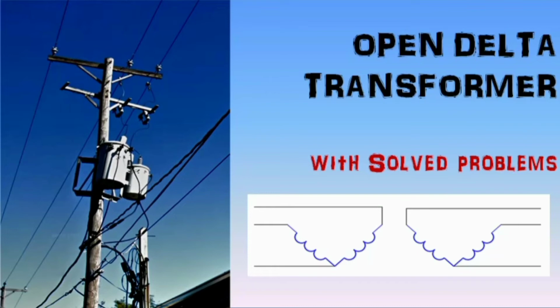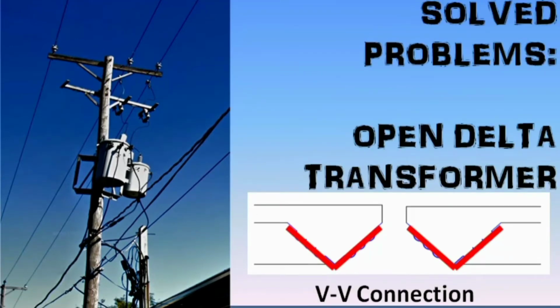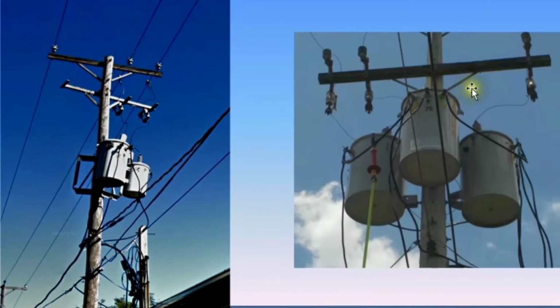Now let's discuss open delta connection of transformers. They also call this VV connection. This system uses only two single-phase transformers to provide three-phase power supply to its loads. Unlike the closed delta transformer banks that have three transformers, open delta connection uses only two single-phase transformers, and both of them can provide three-phase supply.